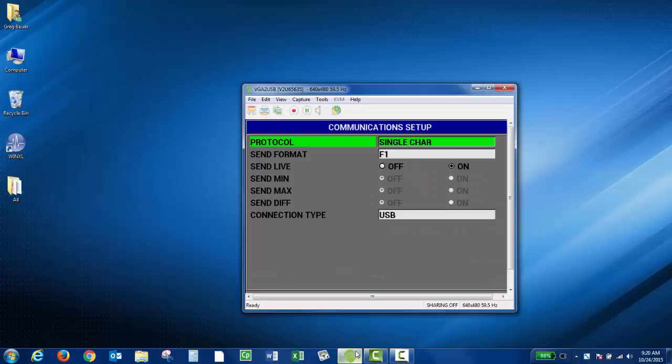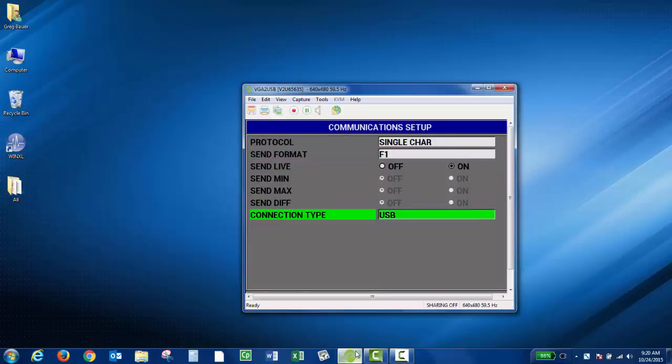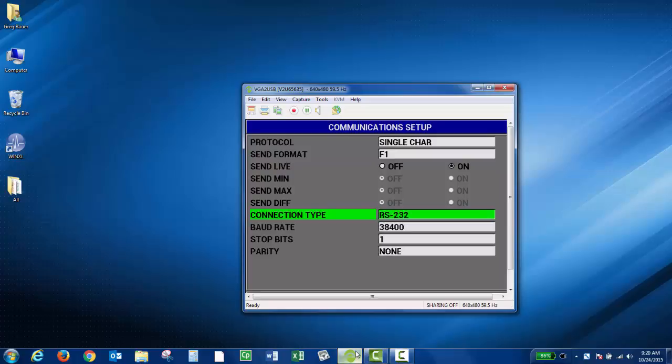Right now the connection type is set to USB, which is kind of the default setting. So you want to press the down arrow and use the right arrow to change that to RS232.